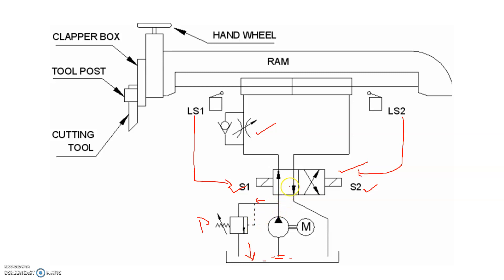Pressurized fluid enters into the direction control valve. The direction valve is controlled by the solenoid by means of limit switches. When the piston rod is extended to its limit, limit switch LS1 will be activated and the solenoid will act on the direction control valve, shifting it to the next position.